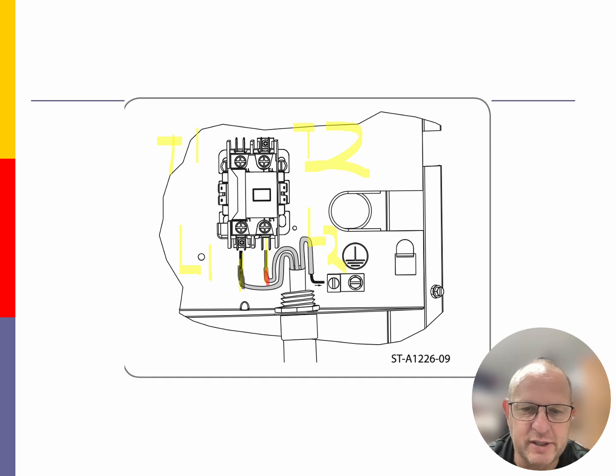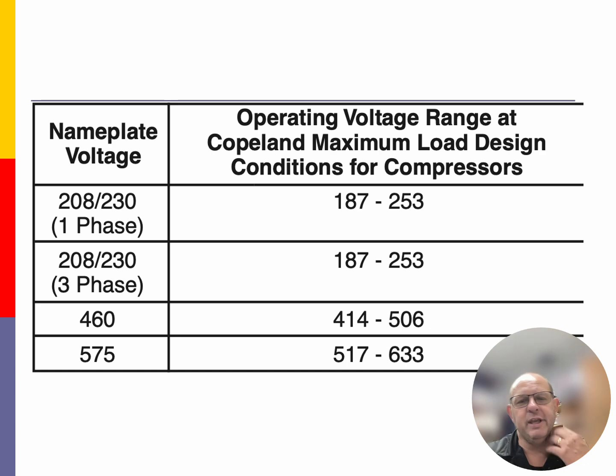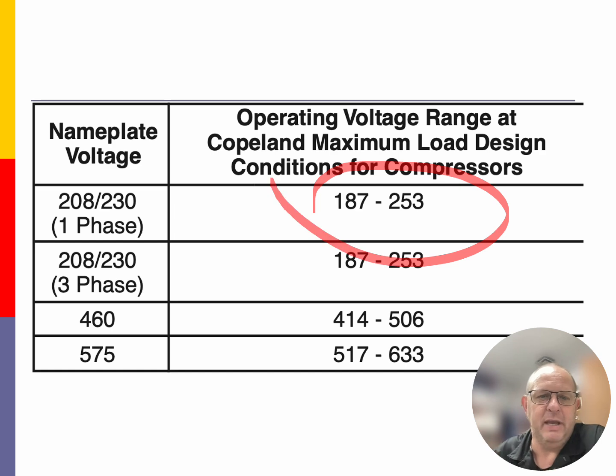Now, when we get into tolerances of voltages on our units, we're looking at what the nameplate voltage reading is for this unit. Based off of that, we have a 10% variance that is acceptable for that unit to start up. So for a single phase, 208/230 system, the acceptable range happens to be 187 volts to 253 volts. Don't want it to drop below that. So we're going to be watching this electric as we are kicking on that unit to see what the drawdown of our actual system is. But our compressor will operate at 187 volts. And if we get too high of a voltage on this particular unit, the tolerance for that is 253 volts. So we have a tolerance of 10% either way on that system when we look at it.